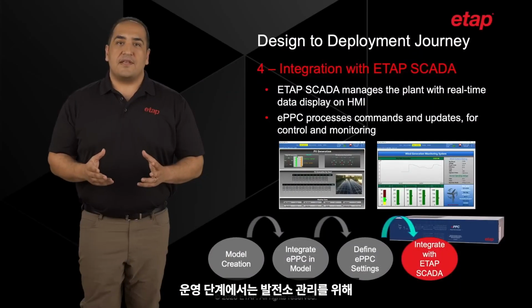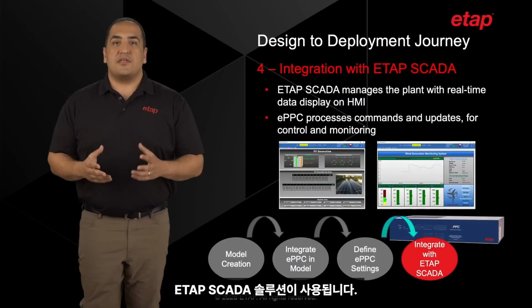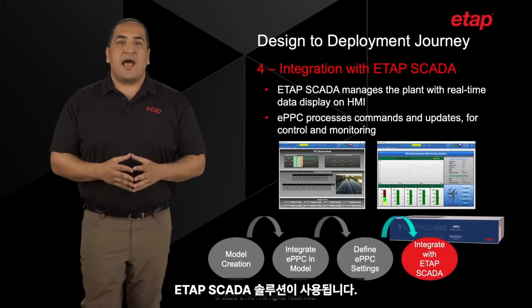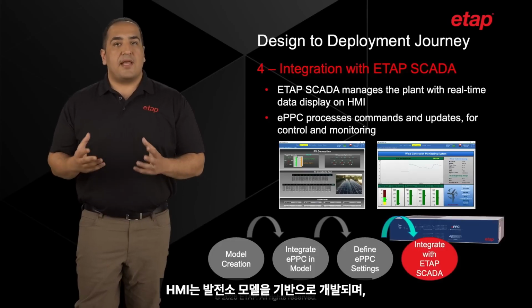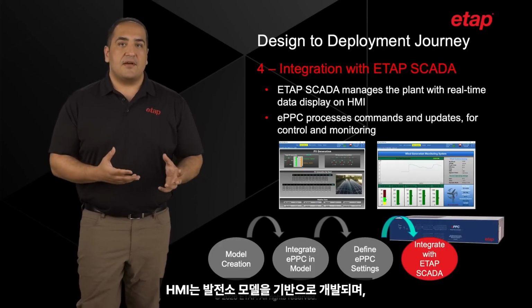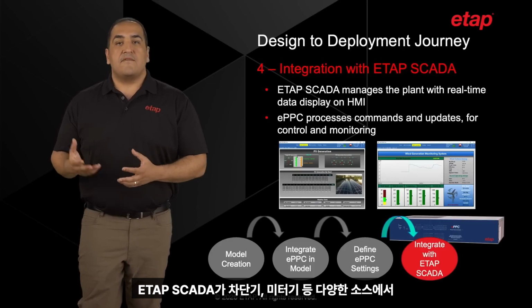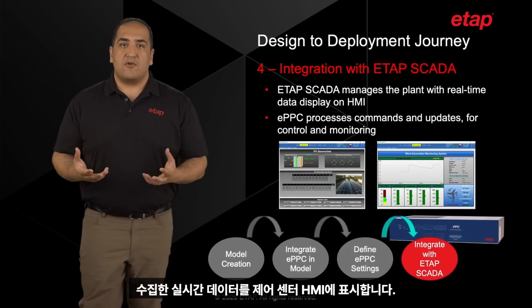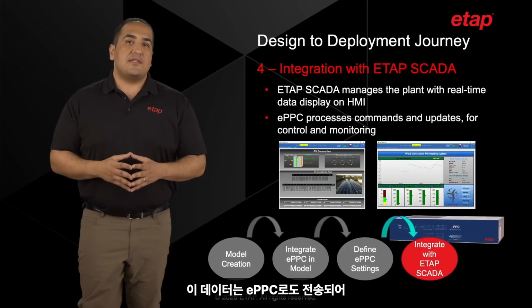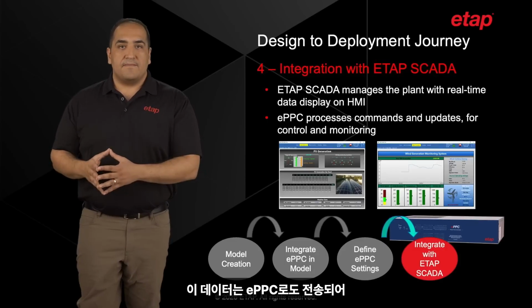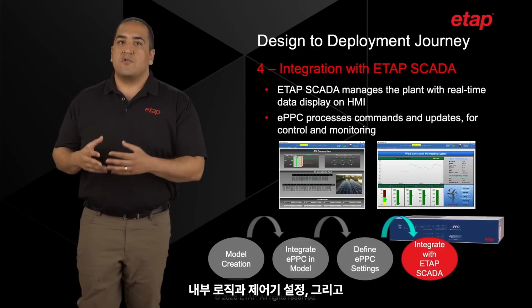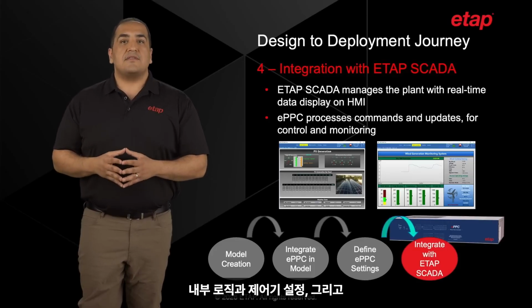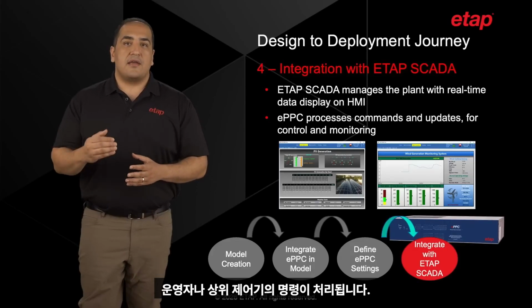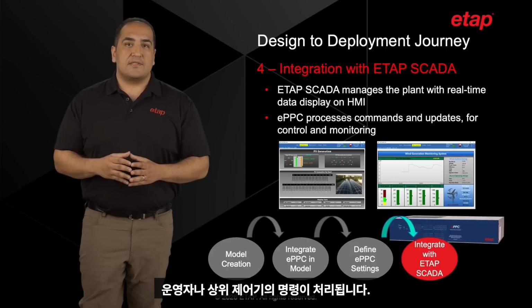During the operational phase, ETAP's SCADA solution is used to manage the plant. An HMI is developed based on the plant's model, with ETAP SCADA acquiring real-time data from various sources such as breakers and meters and displaying this information on the control center's HMI. This data is also fed into ePPC, where the internal logic, controller settings, and commands from the operator or higher-layer controller are processed.